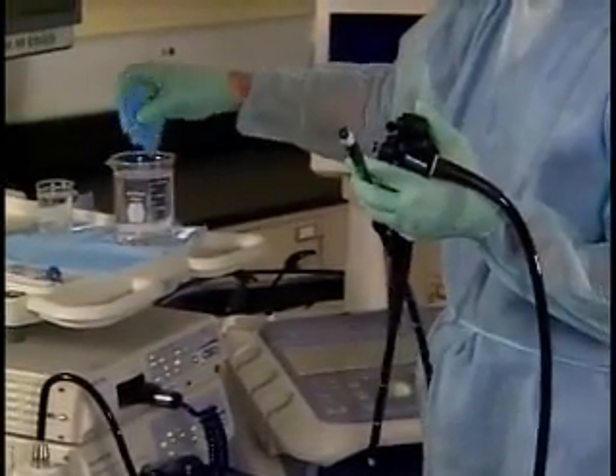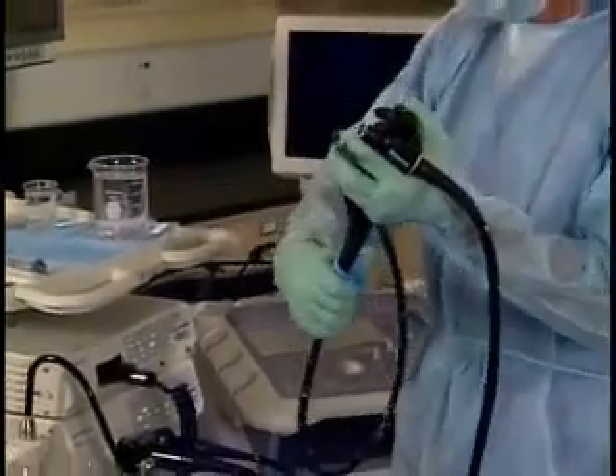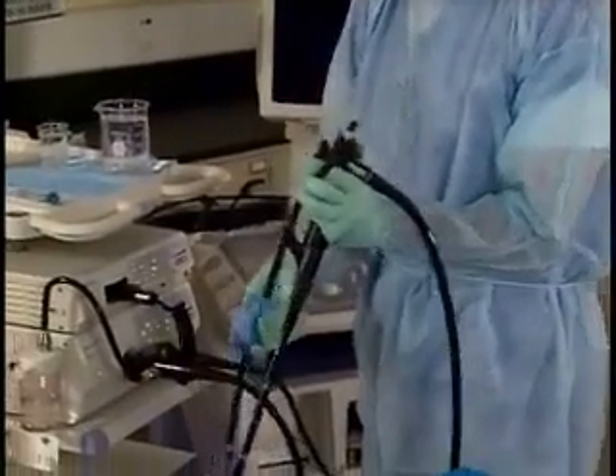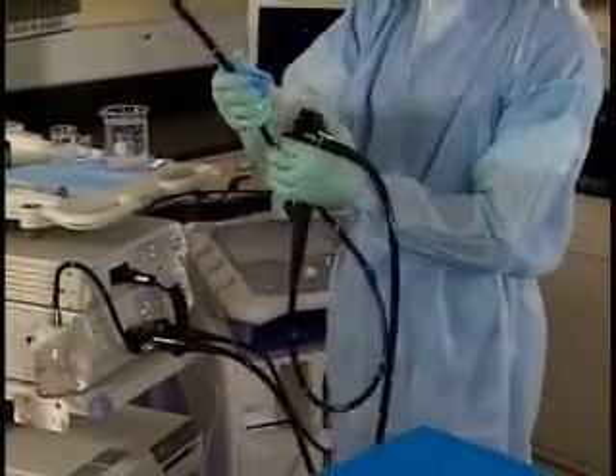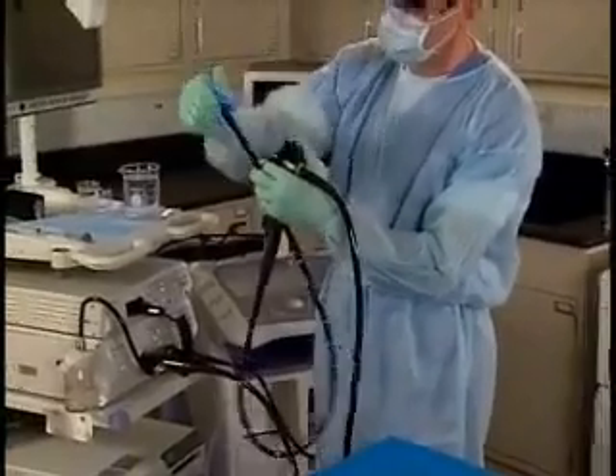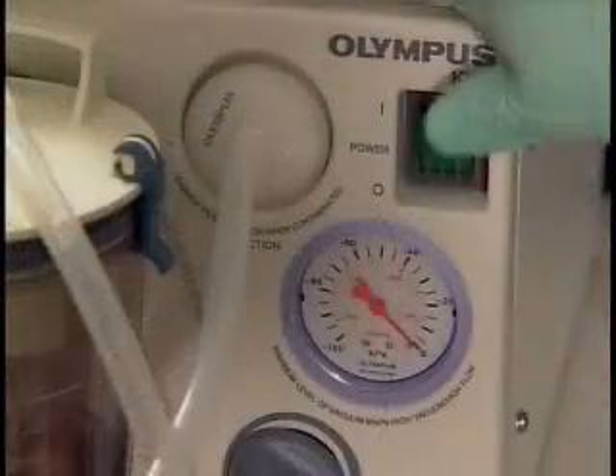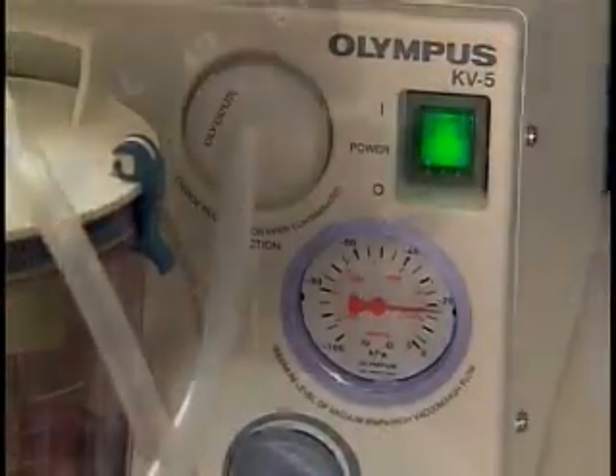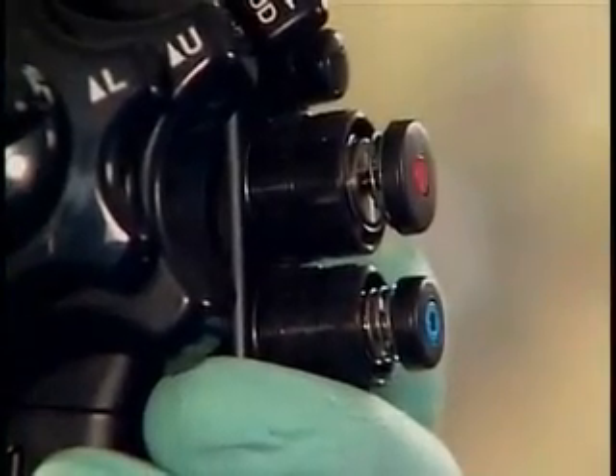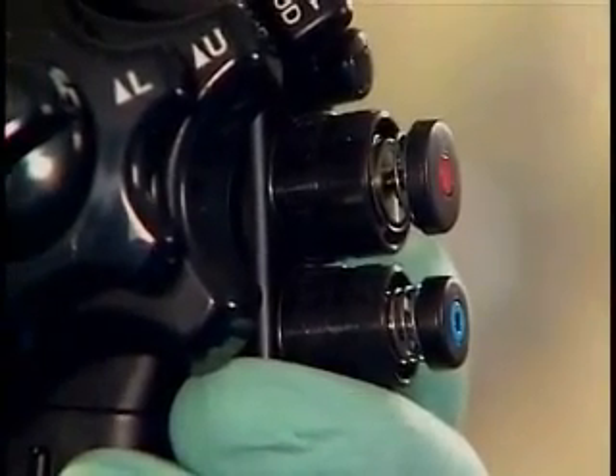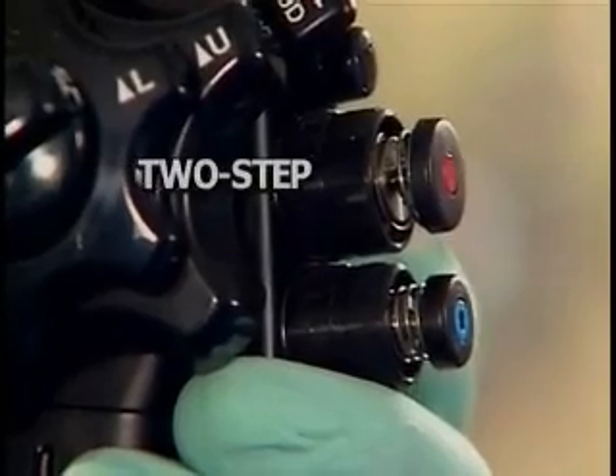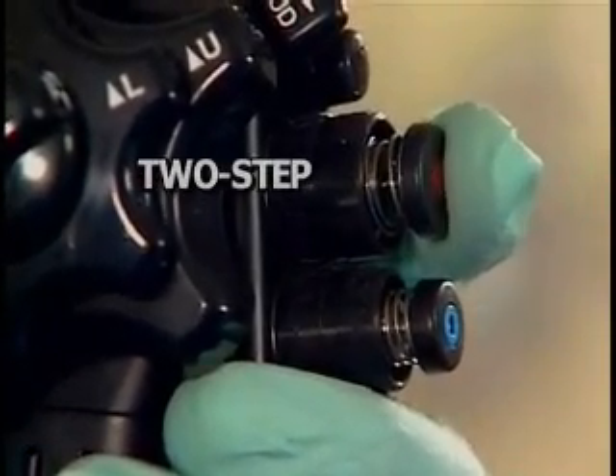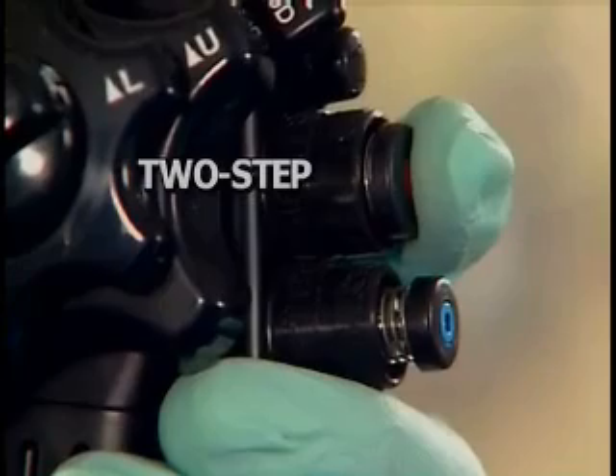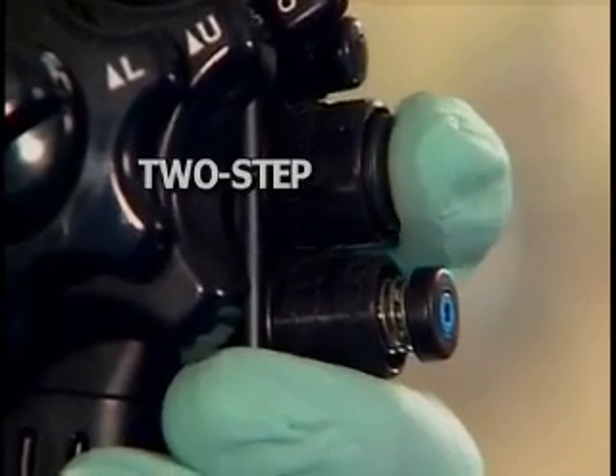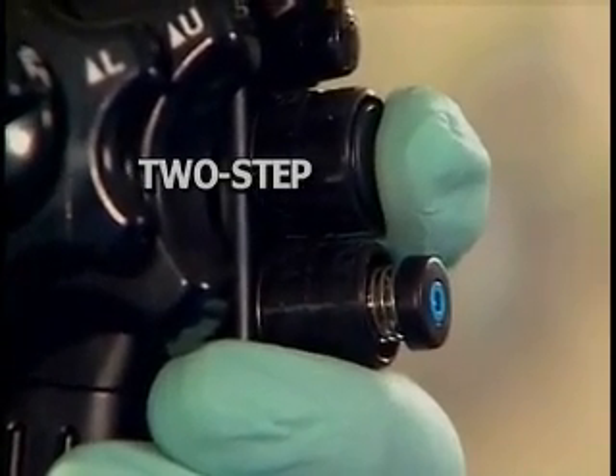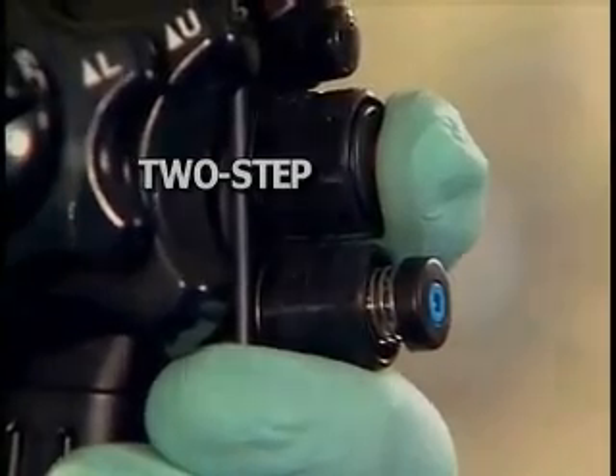Then, gently wipe the insertion tube from the control section to the distal tip with a lint-free cloth or sponge soaked in detergent solution. Turn on the suction pump. Please note that the suction valve in ultrasound endoscopes has 2 steps. The first step, or stage, provides suction through the instrument channel. The second step provides suction through the balloon channel.